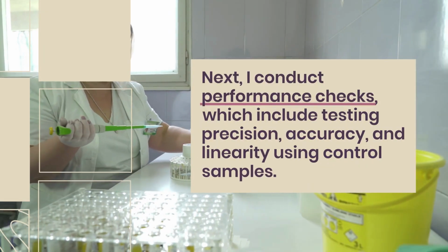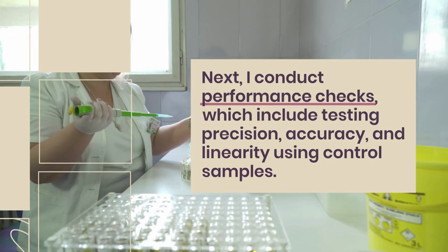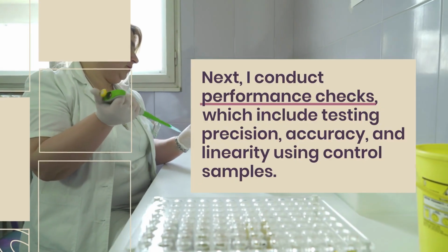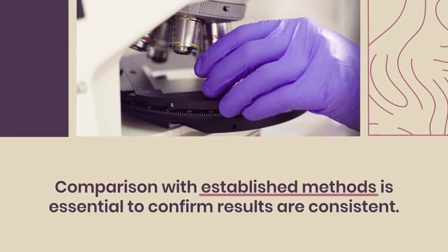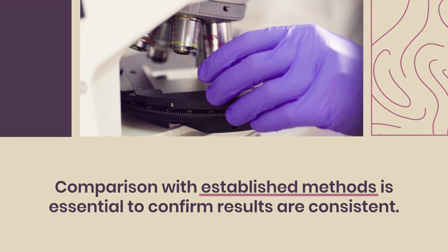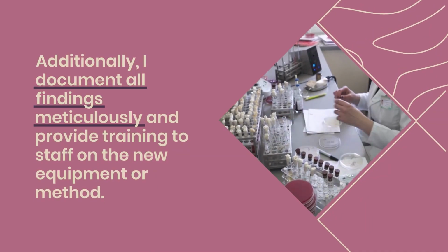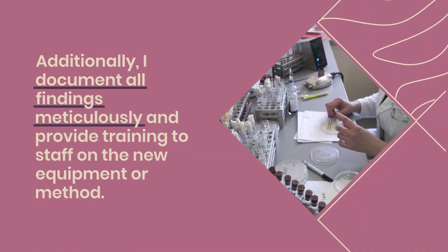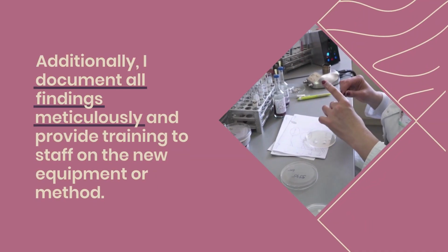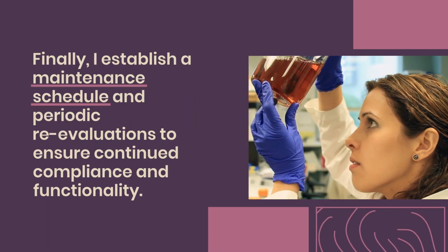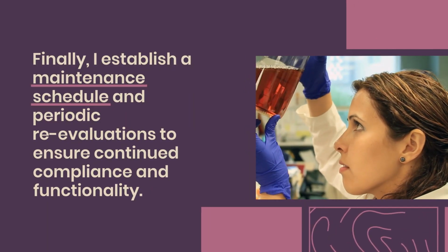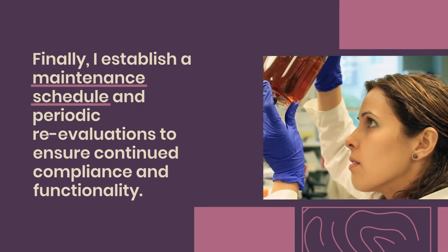Next, I conduct performance checks, which include testing precision, accuracy, and linearity using control samples. Comparison with established methods is essential to confirm results are consistent. Additionally, I document all findings meticulously and provide training to staff on the new equipment or method. Finally, I establish a maintenance schedule and periodic re-evaluations to ensure continued compliance and functionality.